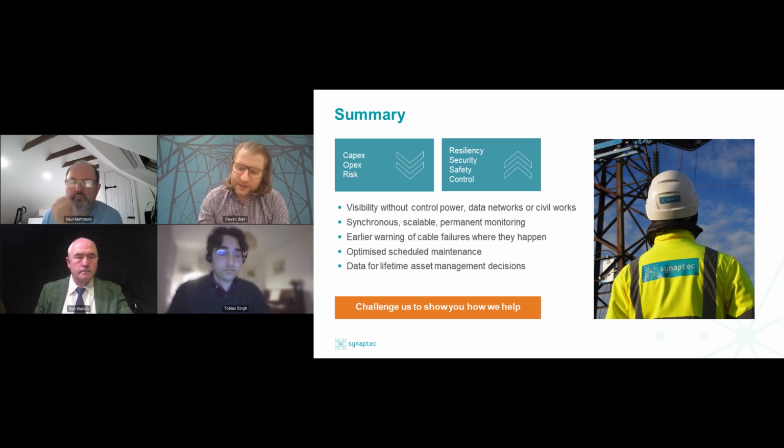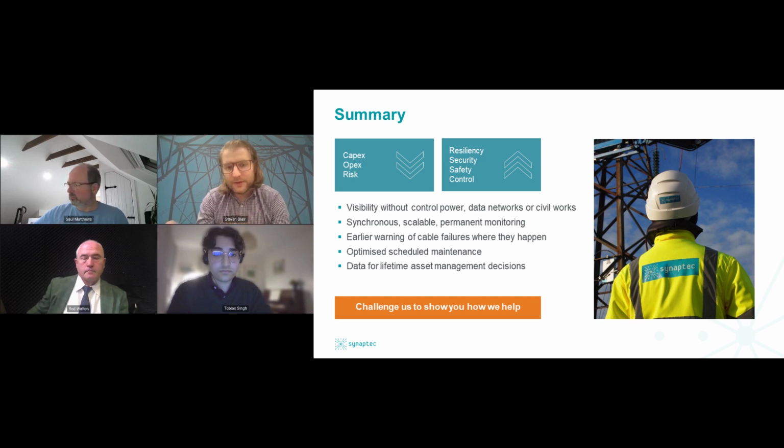What we can also do is, as well as looking at each individual sensor and what it does over time, we can compare one sensor to its peers and see if, for example, one temperature sensor is doing something strange compared to a similar sensor at similar locations, then we can flag that as an anomaly. So that's our approach, is that we're trying to do something new here and expose a different kind of class of alarms that were previously not possible, really.